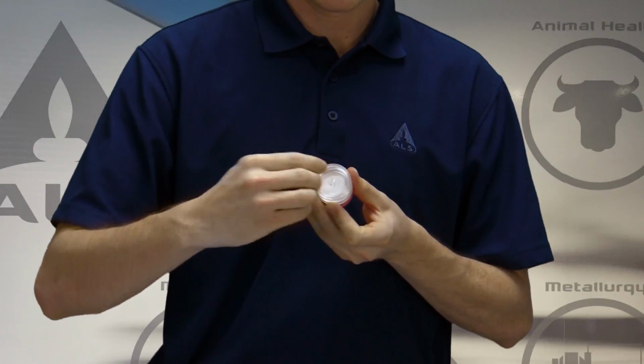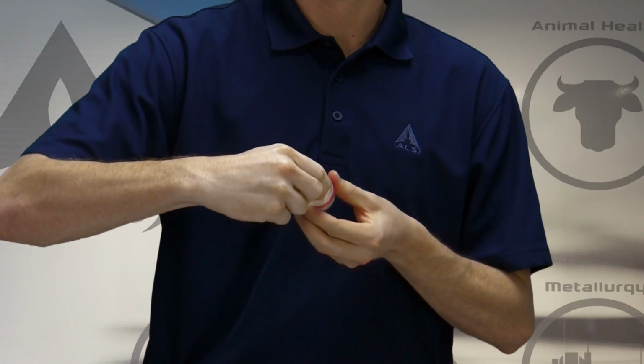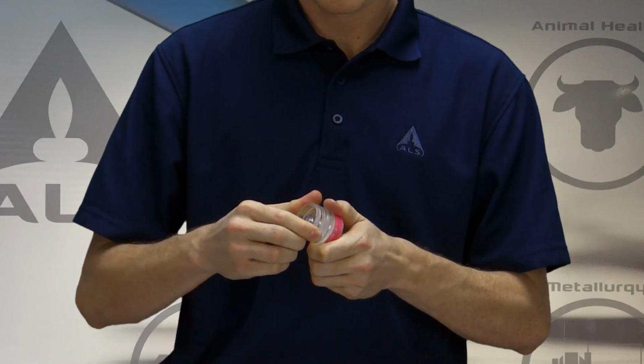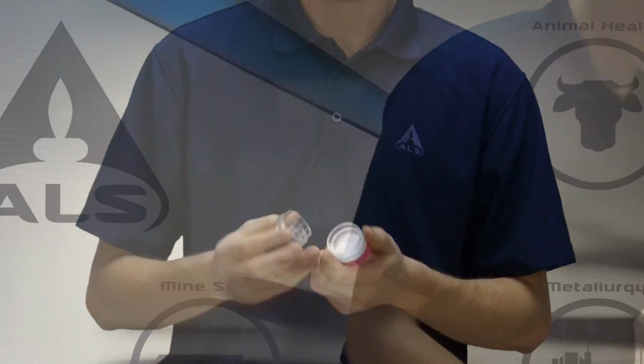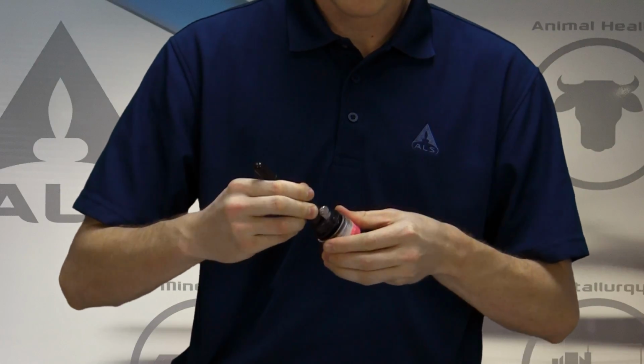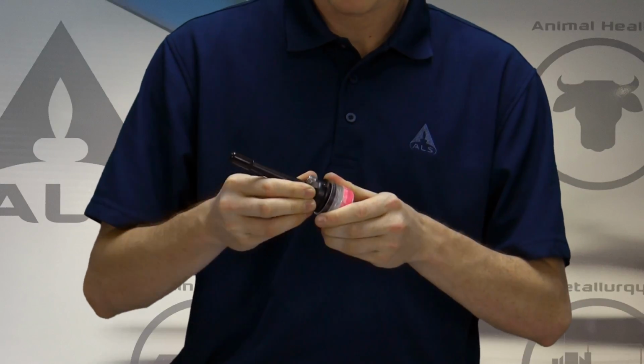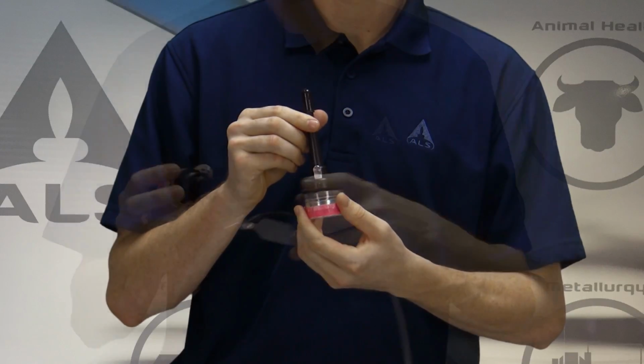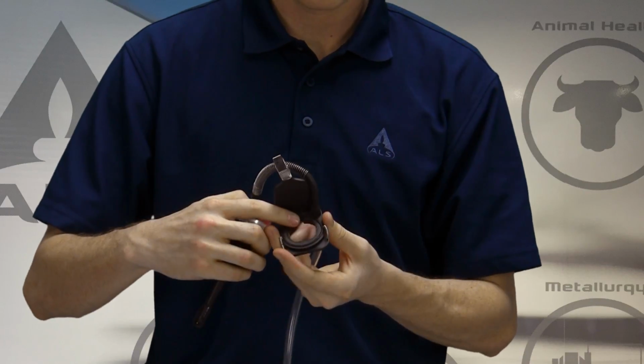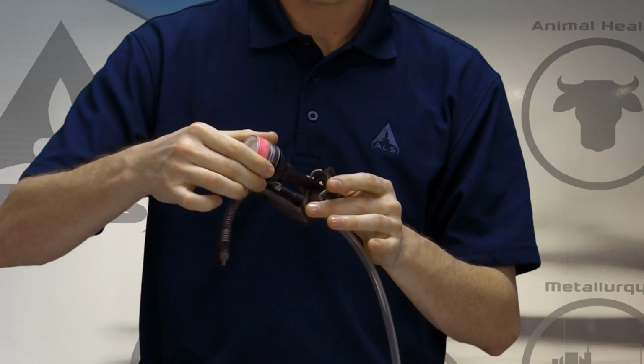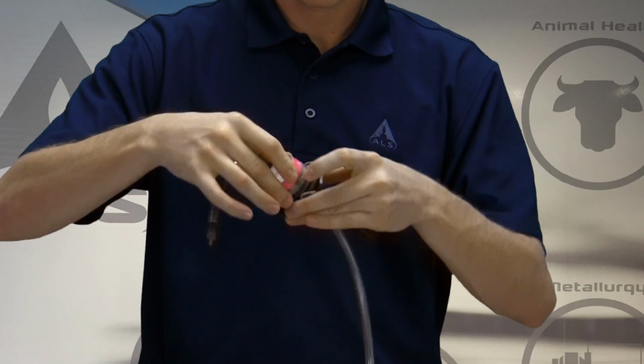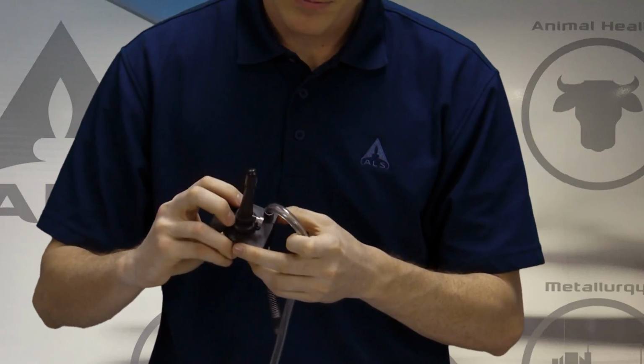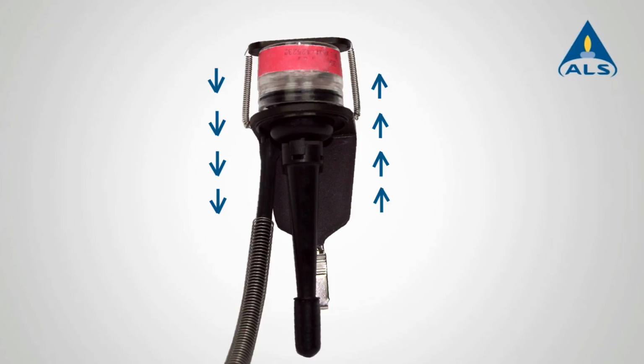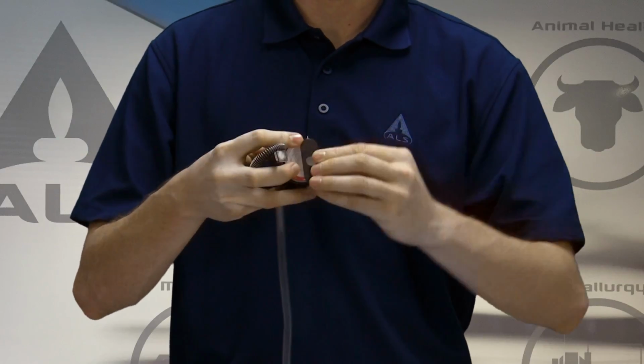Remove plugs from the inlet and outlet of the cassette filter. Remove the inlet section from the cassette, then align and press the cyclone into the cassette's exposed middle section until a firm seal is secured. Insert the cyclone into the holder inlet side down. Please note that the cyclone reference nodule should align and settle into the cassette holder's notch. This will ensure that the cyclone inlet side slits are facing the correct direction to emulate the breathing zone air uptake. Use the spring clamp to hold the cassette in place.